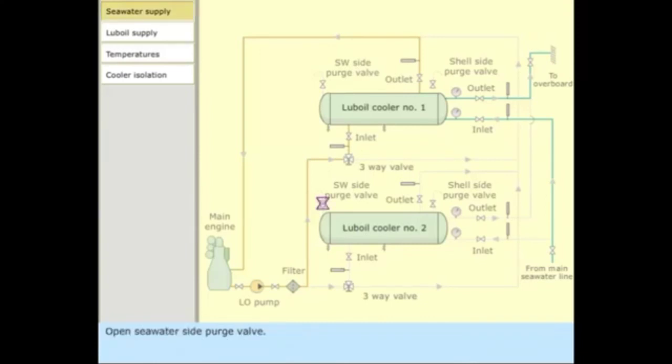Open sea water side purge valve. Open sea water inlet valve by one turn. When the water comes out of the purge valve, open the sea water outlet valve gradually to full open position. This will ensure that no air is trapped in the sea water side. Close the purge valve. Open the inlet valve fully.